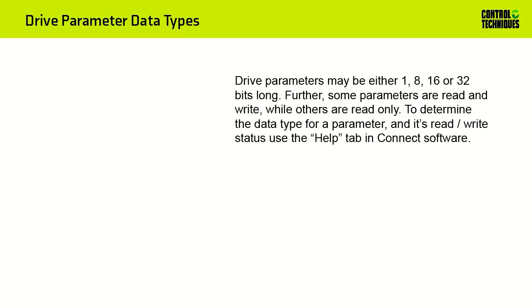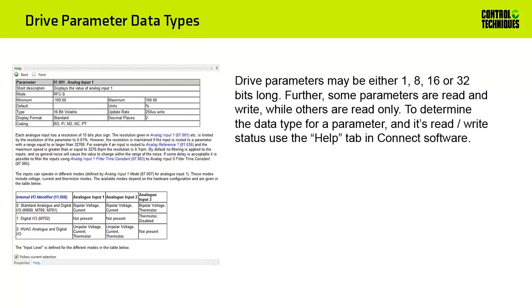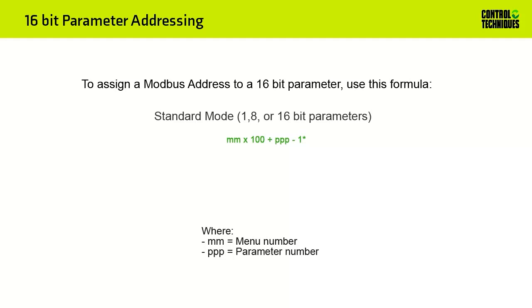Some parameters are read and write while others are read only. To determine the data type for a parameter you'd like to access using Modbus and its read-write status, refer to the Help tab in Connect Software as shown here. This is menu 1, parameter 21. The first thing you'll notice is its type — this particular parameter is 32 bits long. In the coding field, you'll see the abbreviation RW, meaning the parameter is read and write. To assign a Modbus address to a 16-bit drive parameter, use these formulas.